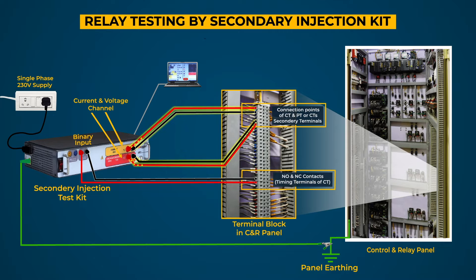Finally, by pressing the test start button, testing begins and after completion of the test the results are displayed on the screen. This testing data may be recorded for checking the performance and characteristics of relays. If the results are beyond the permissible limits, recalibrate the relay; or if defective, replace the relay.